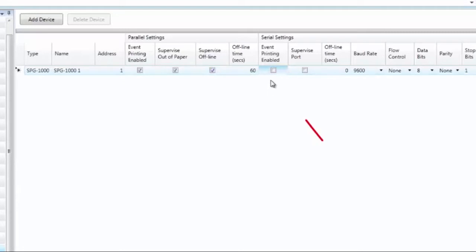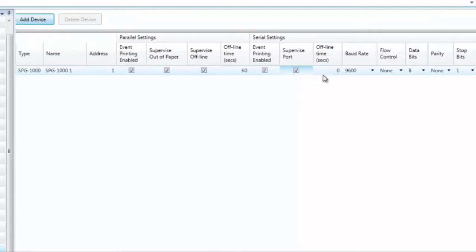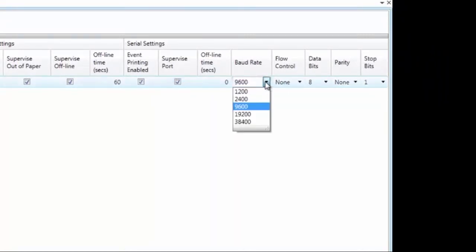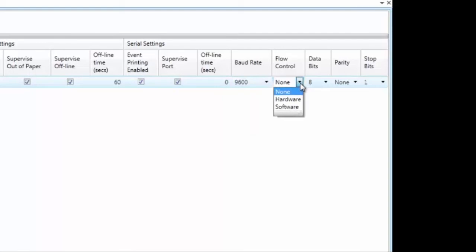If connected to a serial printer, select the box to log events to that printer. If Supervised Port is selected, the SPG1000 continuously monitors for the presence of the serial printer; if not connected, a trouble event is enunciated at the panel. With Supervised Port selected, you can set the offline time — the duration before the trouble is generated, with a default of 0 seconds. You can also adjust the baud rate, which is the rate for transmitting data to the printer. The default is 9600 baud, with options from 1200 to 38,400 baud. Under Flow Control, you can select None, Hardware, or Software — refer to the printer's specifications for the proper setting. The default is None.